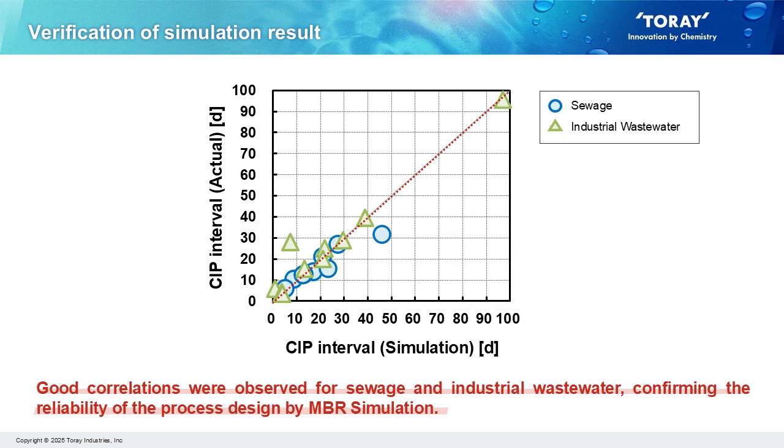This slide shows the verification of the TMP simulation. We verified our simulation technology with sewage and industrial wastewater cases. As you can see, good correlations were observed for sewage and industrial wastewater, confirming the reliability of the process designed by MBR simulation.